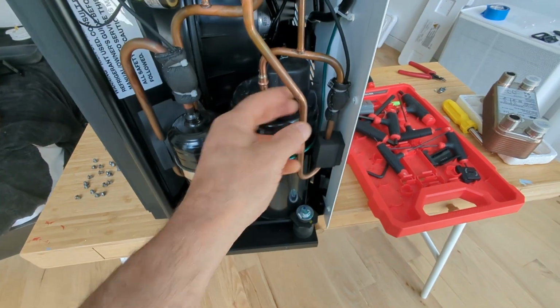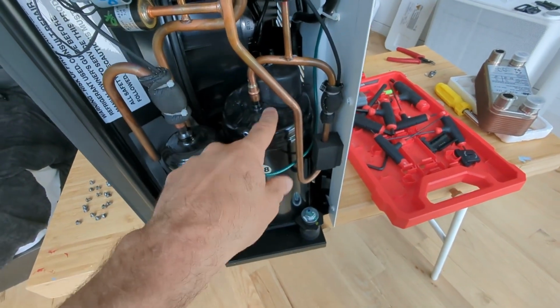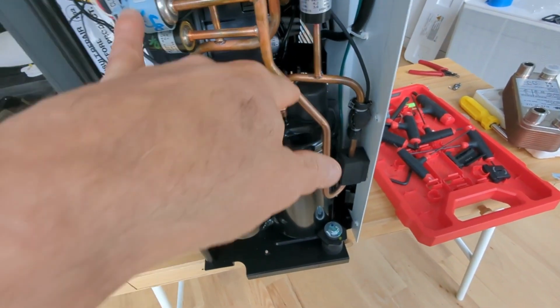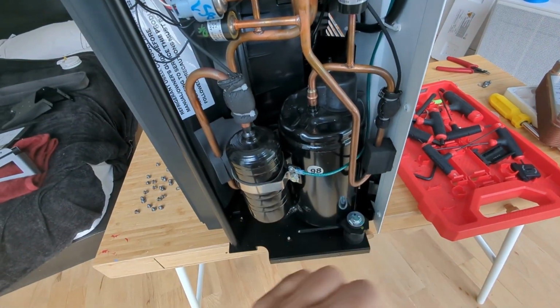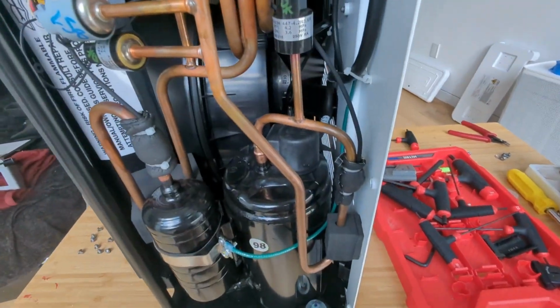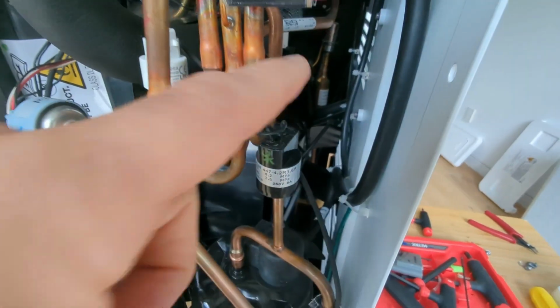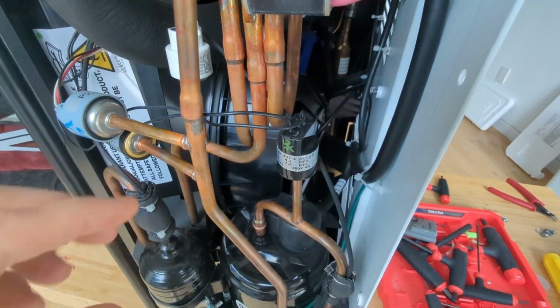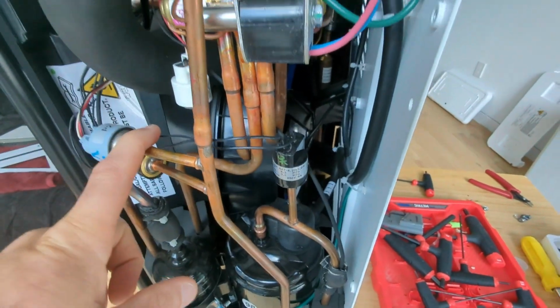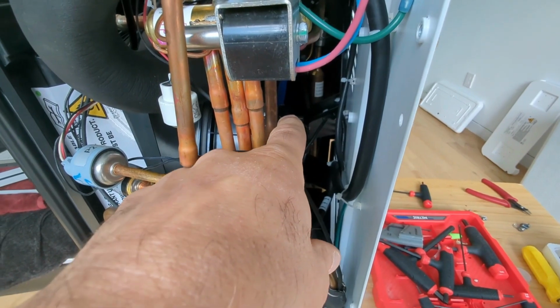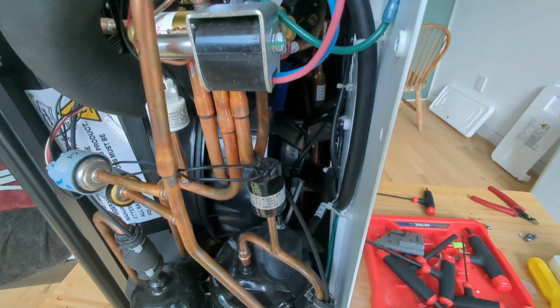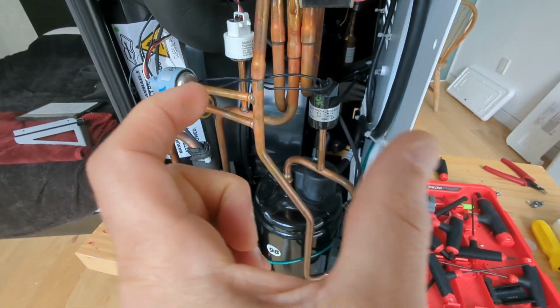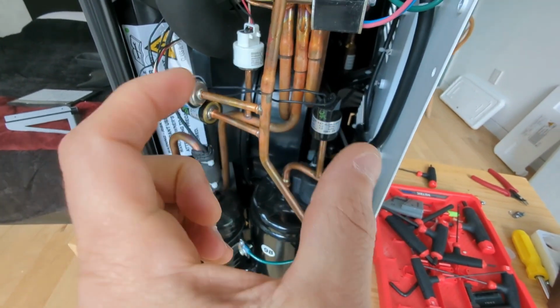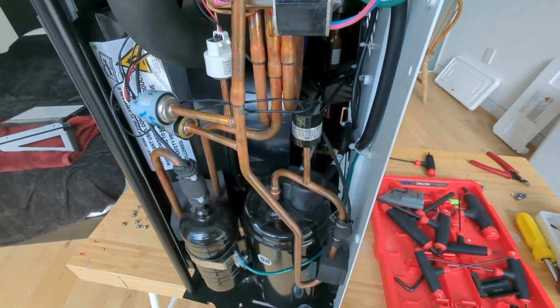These foam blocks here just prevent some of the vibrations from this compressor from getting up into the rest of this piping. So it keeps everything from rattling around. In there, you can see the fan that's blowing over the condenser coils. Kind of interesting fan. So it runs on 120 volts, but it has a digital pulse width modulation line that goes up to the controller. And so the controller changes the duty cycle of that PWM signal to change the speed of that fan.